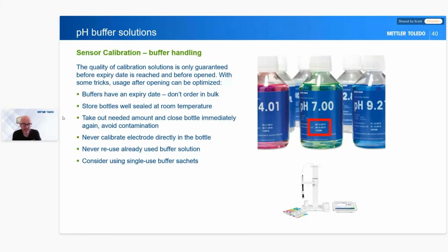We always take buffer solutions out into a smaller bottle and then measure into a small capsule or a small bottle, never directly into the solution. The other thing is we never keep that little bit. Once we take a pH measurement, a calibration and adjustment, once we've used that buffer, we throw it away, because that little piece can become contaminated. The next time we do a buffer, we decant some fresh solution, use the fresh solution and then throw it away. That's really important to keep the measurements accurate, keep the calibration accurate.